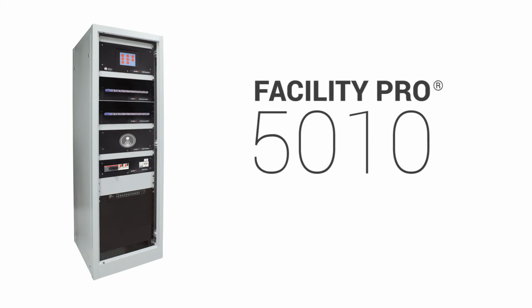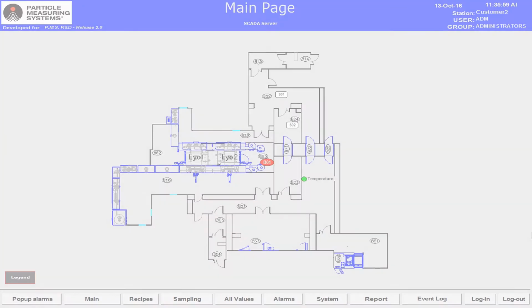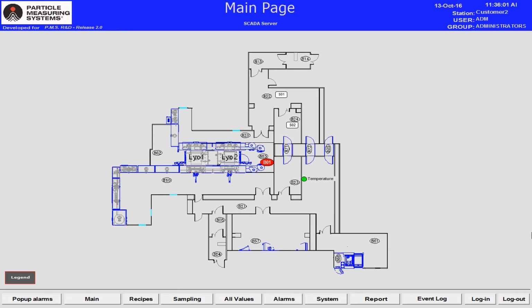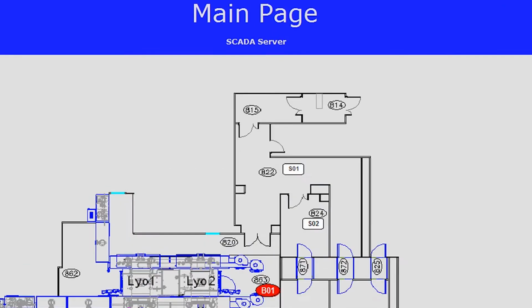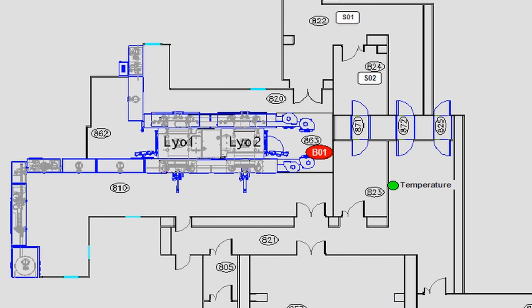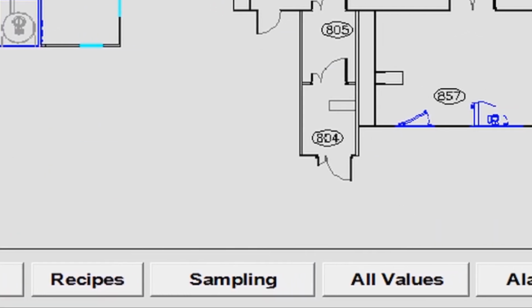The Facility Pro SCADA software is based off the GE iFix platform. SCADA stands for Supervisory Control and Data Acquisition. This system allows for complete monitoring and control of the Cleanroom environmental monitoring system, as well as generation of reports of the system's operation. The main page consists of 3 sections: the header, the display area, and the access tabs for system operation and control.